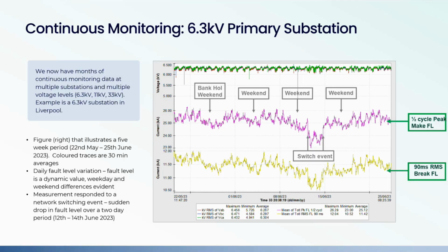About two-thirds of the way across the graph, you can also see a step change in fault level where there was a network switch event. So the network topology changed. That resulted in a step change in the fault level. And then you see the same sort of variability as before until the network was returned to the original topology, and you get that step change again in the other direction.